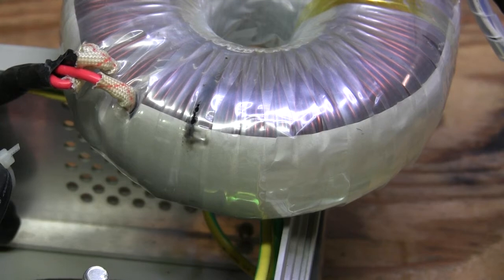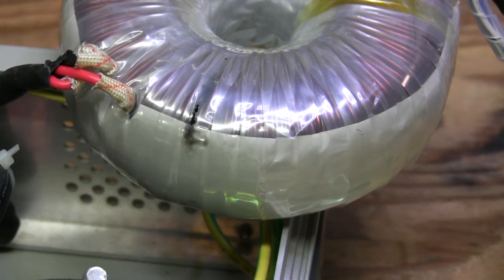Is this good or bad? On the one hand, this certainly looks repairable, and probably nothing else is wrong except the transformer. On the other hand, rebuilding this transformer can be a lot of work, and it depends largely on where the damage is. If it's just on the surface affecting the secondary, that can be quite easy. But if it's very deep, affecting all the windings, primary and secondary, then I need to remove everything and put a new wire in place, which can be a lot of work.